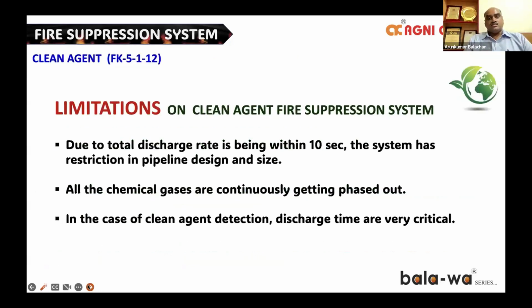The limitation of an FK system or the chemical system is that it is to be discharged within 10 seconds, which means the system has a restriction in pipeline design and size. In large data centers, we cannot have a centralized bank. Banks have to be in multiple locations for a large data center. And during a crisis, it might be very difficult to go to different places and activate the system manually if the automatic system fails. And one of the other limitations with a chemical agent is that many times chemical gases are continuously getting phased out because these are chemicals manufactured specifically for the purpose of firefighting.